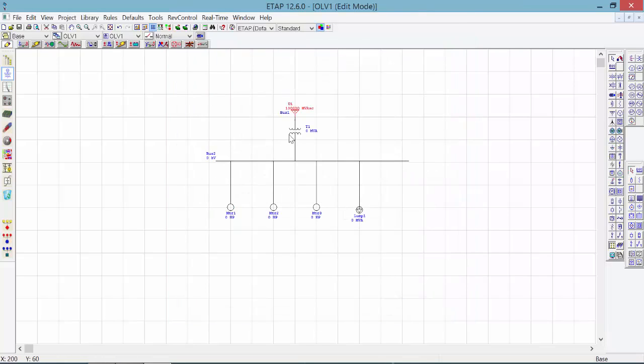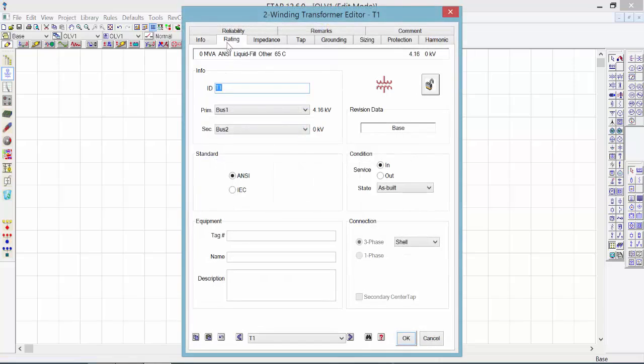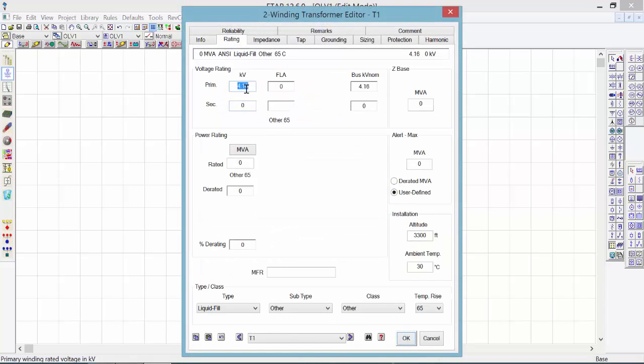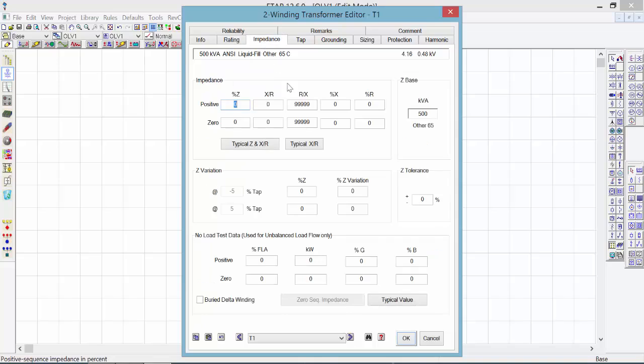and click on OK. For the transformer, the primary side is already chosen, and the secondary side, let's put it 480. One of the most used voltage levels in the industry. And let's put 500 kVA. And for the impedance, as always, 6%. And let's fill the rest as typical information. And click on OK.